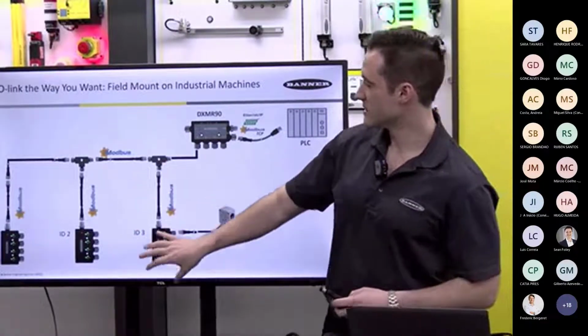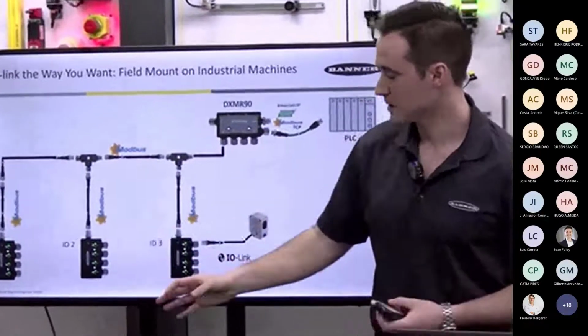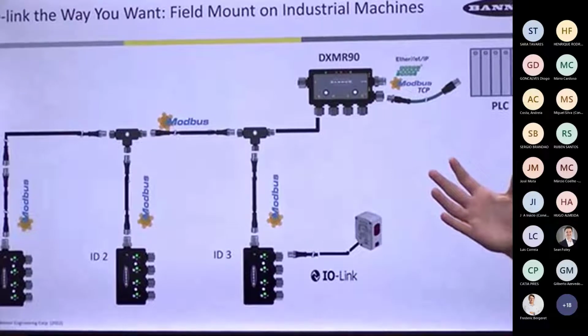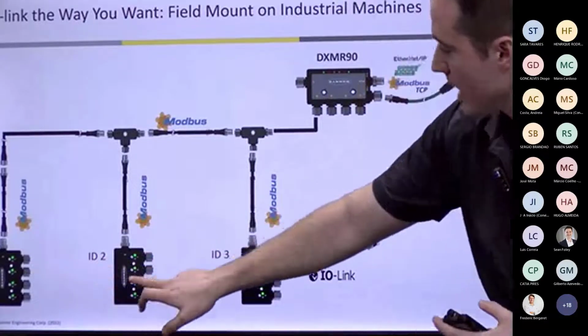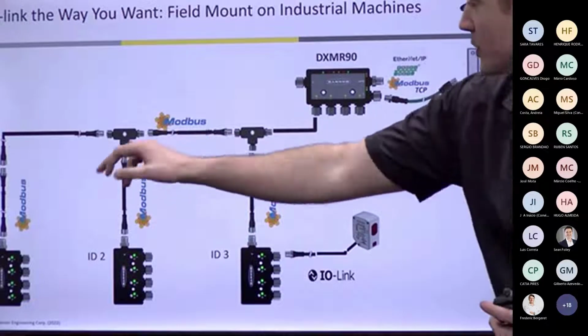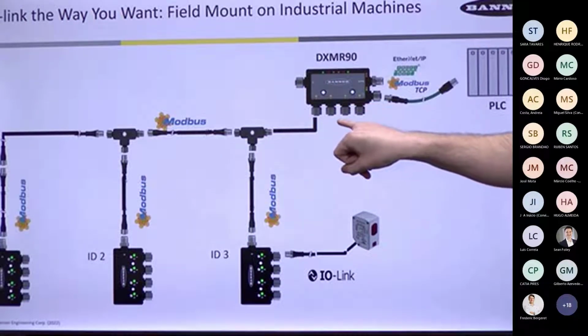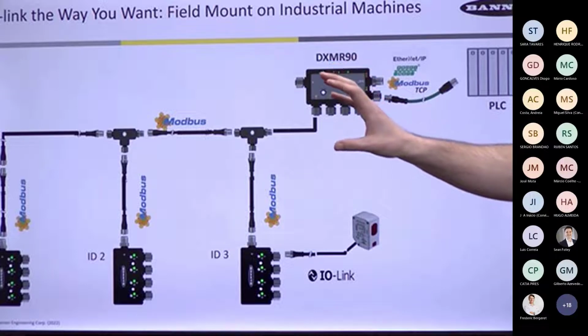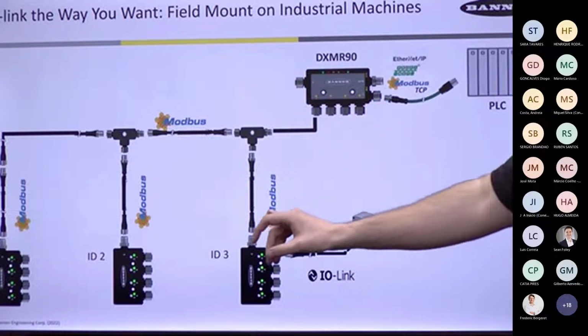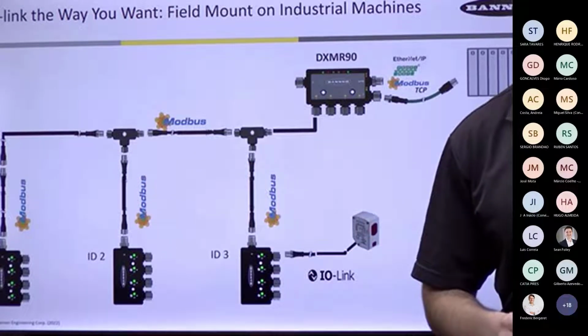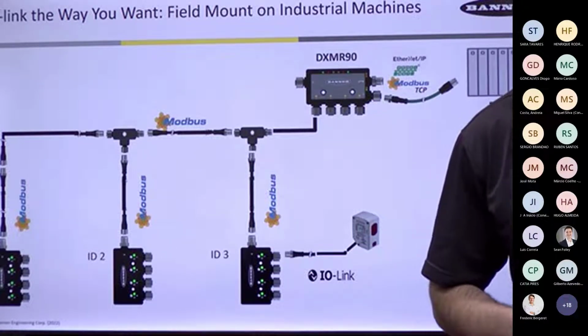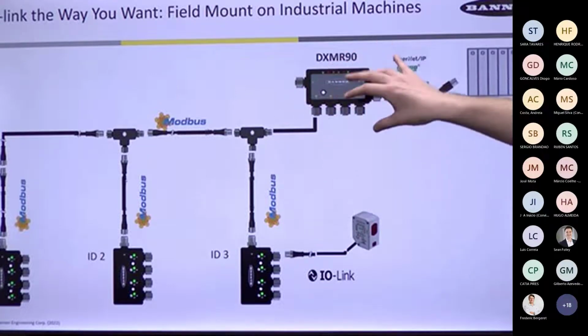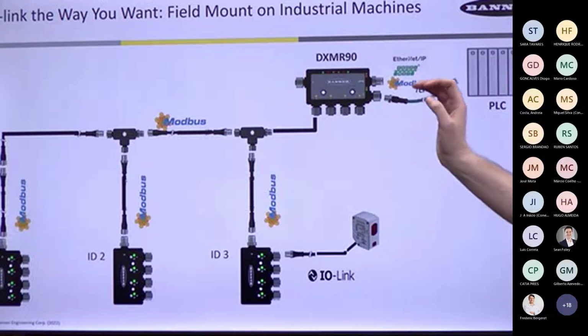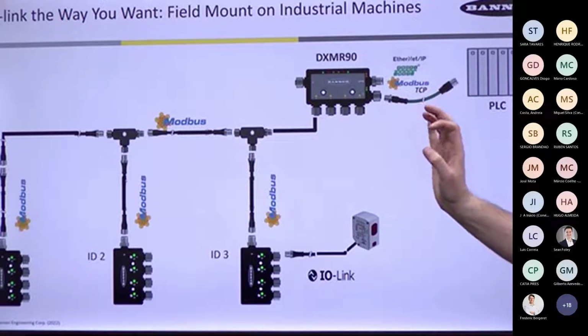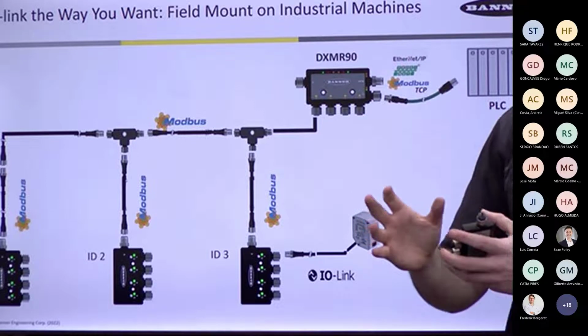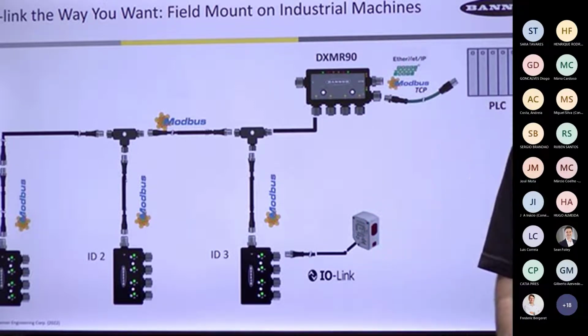Another benefit of this setup, with RS-485 or Modbus RTU infrastructure acting as the method for gathering data, is that you could have multiple IO-Link masters connected on a single branch going back to an individual port on the DXM R90, so large numbers of IO-Link devices could be connected. This RS-485 protocol is a really robust method of gathering data, because in the end we're essentially communicating EtherNet/IP, PROFINET, or Modbus TCP. It's simply the conduit, a robust way of gathering the data.